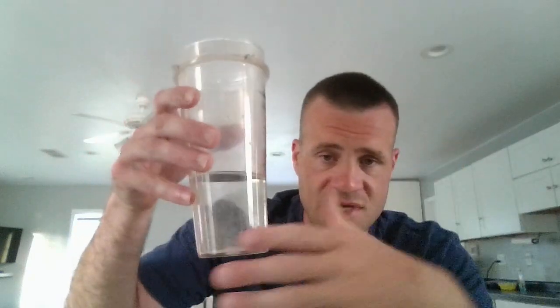So if phosphorus is soluble, it's in the water, and we want to use biological processes, or a combination of biological, or we would add some sort of chemical to convert it to a particulate form. That way we can remove it through either solids settling or run it through a sand filter or a gravity filter, whatever we want to do.